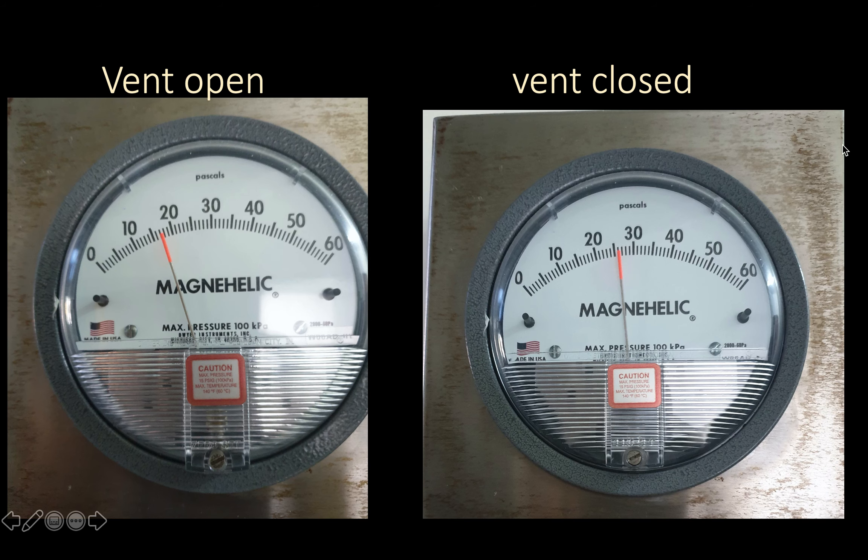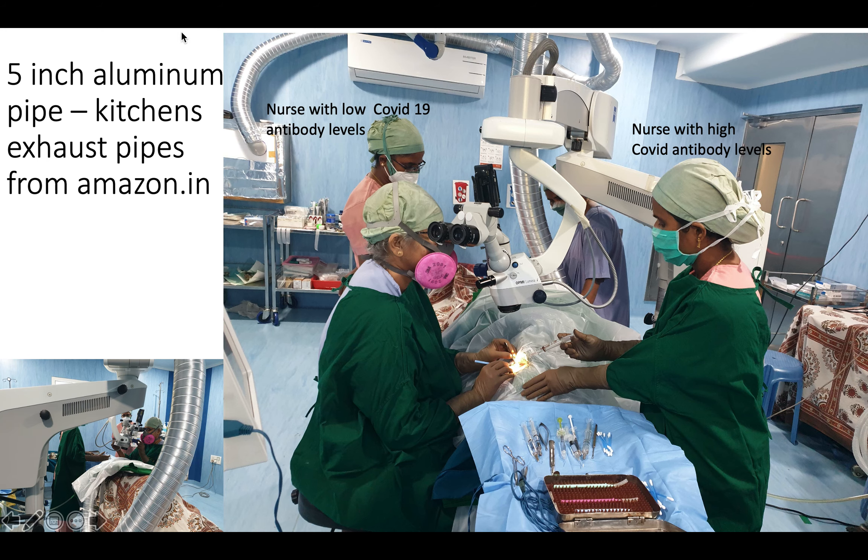The pressure inside my OT is around 25 to 27 Pascals before the exhaust vent is open. After the vent is open, it drops to about 17 Pascals — approximately a 10 pascal drop — and that pressure differential is what drives air from the OT through the pipes to outside. These are 5-inch pipes normally used in kitchen exhaust ventilation systems. Each pipe comes in a 5-foot compressed form and can be expanded to about 12 feet.